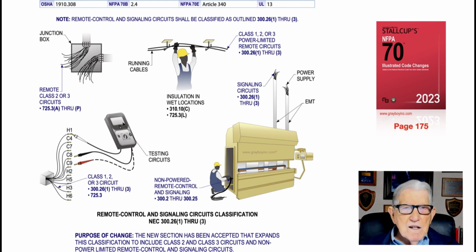But now if you're dealing with a Class 1 circuit, it used to be in 725.41(A) for power limited. But now it's in Article 724, and the exact section number is 724.40, approximately page 659. And they operate at 1,000 volt-amps or less at 30 volts or less. But now dropping down to your non-power limited remote control, with the individual pulling those into that piece of equipment, 300.2 through 300.25 talks about non-power limited circuits.